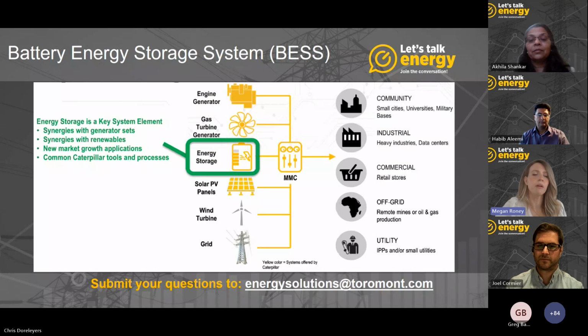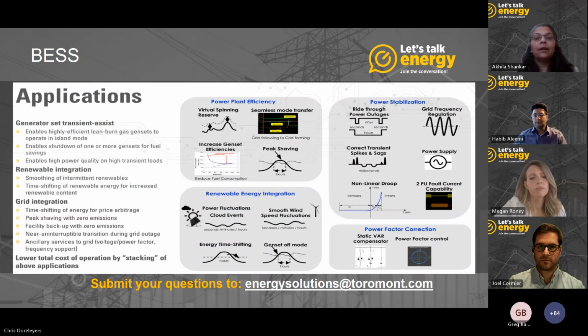Great. Thanks, Akhila. Can you elaborate on the synergies between a BESS with generators, renewable power sources, as well as the utility? Sure. If we can go to the next slide, please. A lean burn natural gas generator set has poor block load acceptance capability. So in the absence of grid power or power from battery energy storage systems, a lean burn natural gas genset can stall when more than 30% of its rated capacity is added as a load in one step. The battery energy storage system enables the lean burn natural gas gensets to operate in an island mode. Also, when you have battery energy storage systems with multiple generator sets, the stored energy from the batteries can be used, so one or more generators may be shut down to save on fuel consumption.